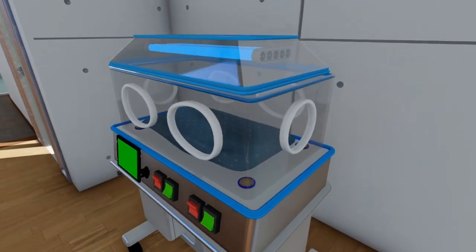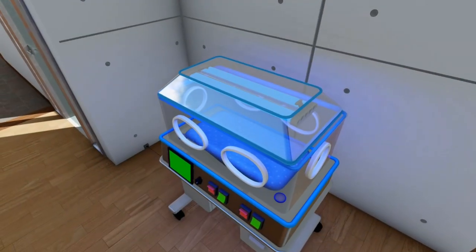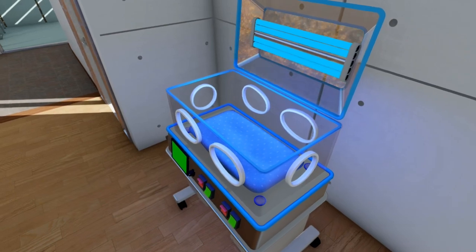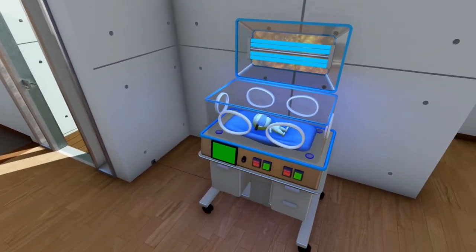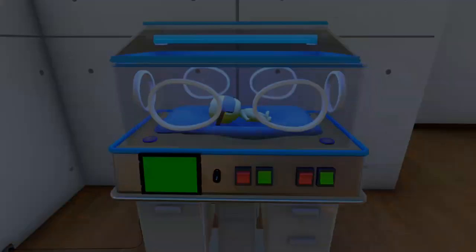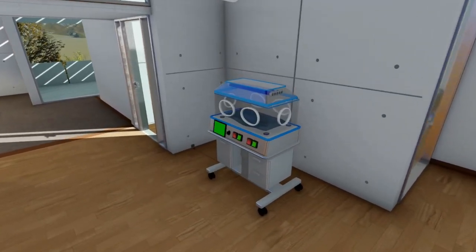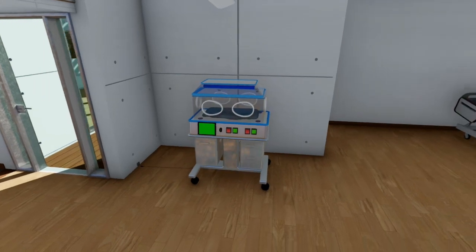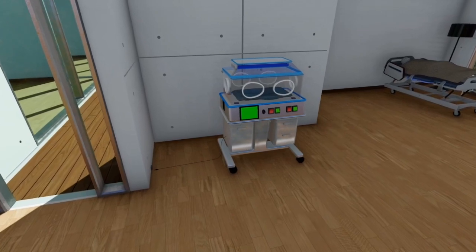The heating system can warm both normal and premature babies. Users can monitor the temperature and humidity produced by this multi-function incubator. When the babies cry, a mechanical swing system works and calms the baby. The light therapy system is used to reduce the baby's bilirubin level. The system is equipped with blue light and daylight lamps, where the daylight lamps work to neutralize the blue light. When babies cry, the mechanical swing system works. This system can be managed and monitored via a web monitoring system.